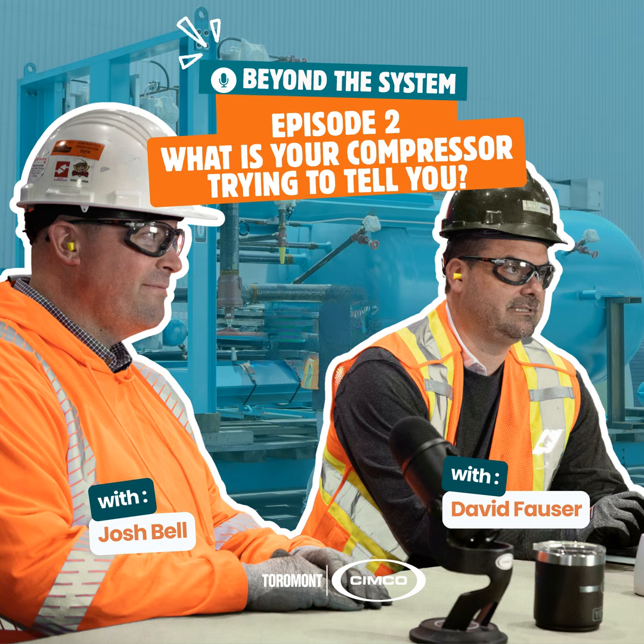Makes sense. And they're essentially just like a pump, right? I mean, you were talking earlier about high pressure and increasing pressures and heat, et cetera. But really, they're just pumping the refrigerant throughout the refrigerant cycle, correct? Yeah, they're pumping refrigerant vapor. One thing that has to be known, you cannot compress liquid. So that's why we have heat exchangers with vessels above them. Those vessels allow for separation of liquid and vapor, and they provide the protection to the compressor.